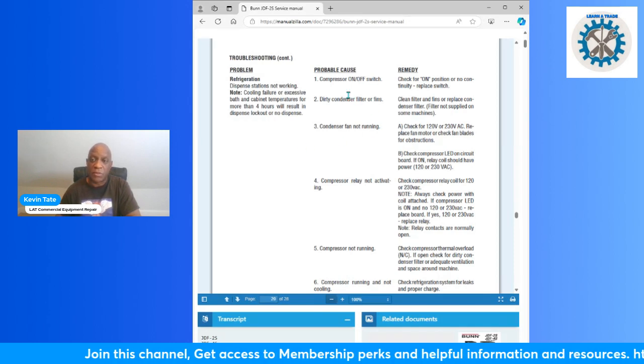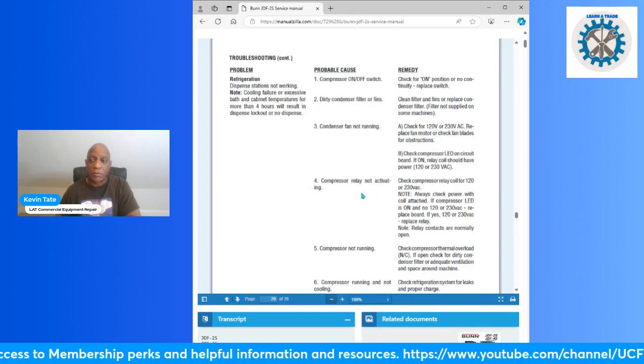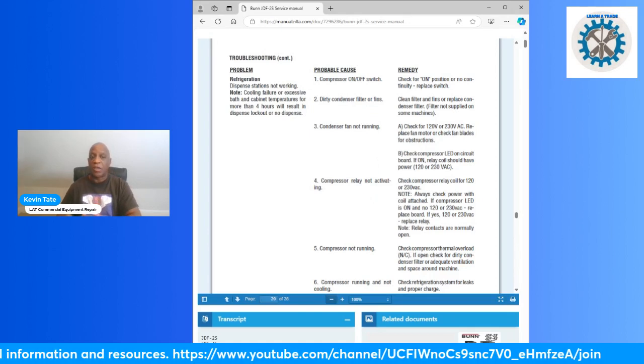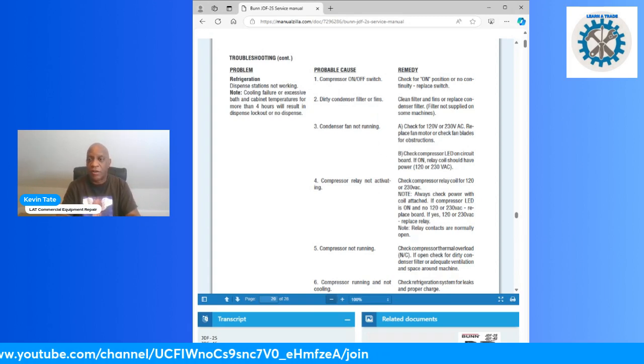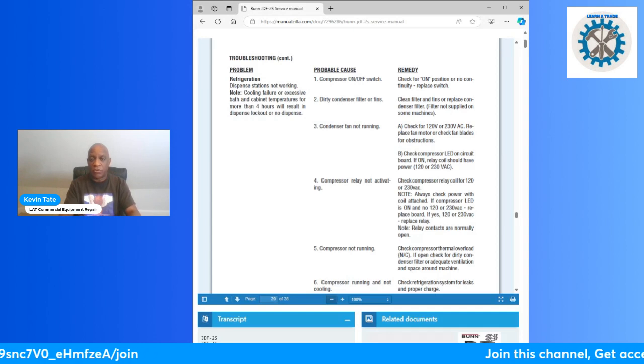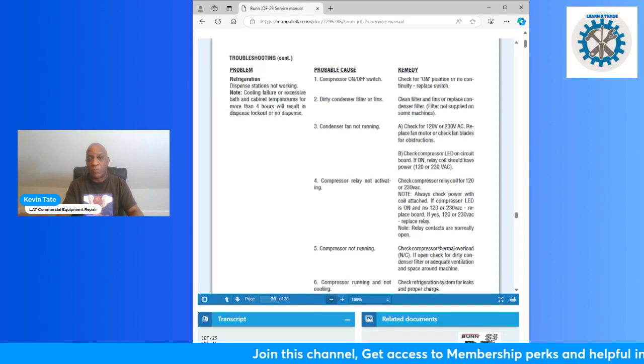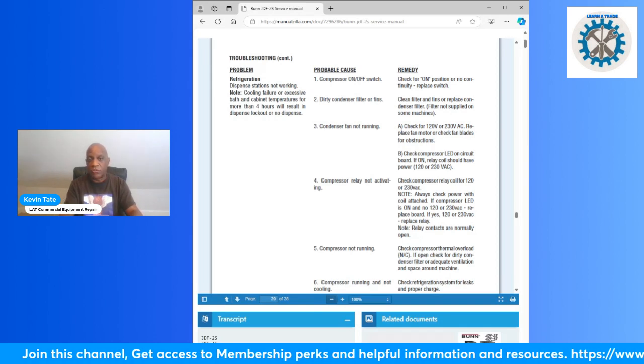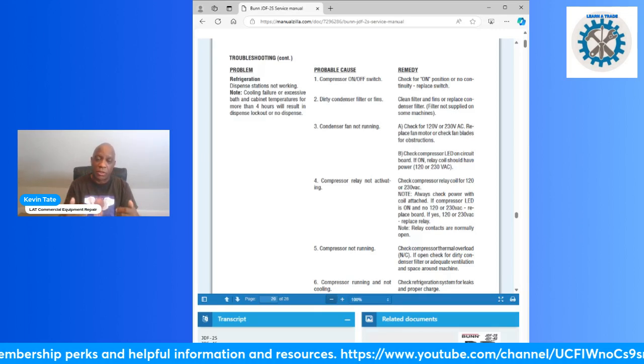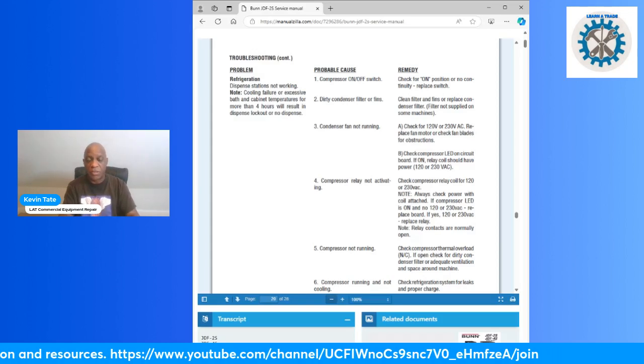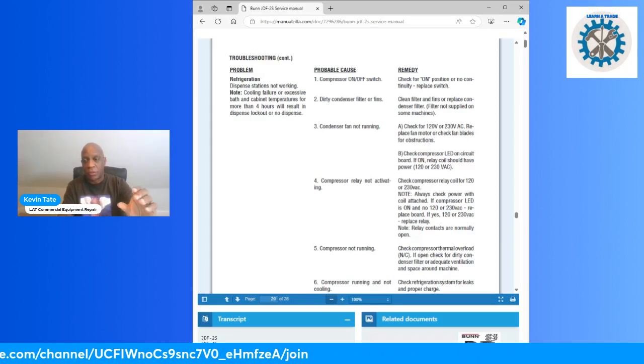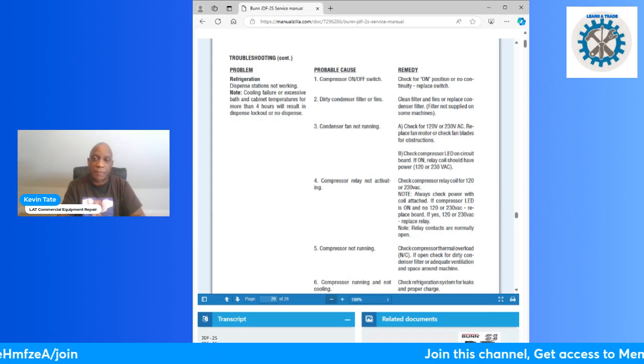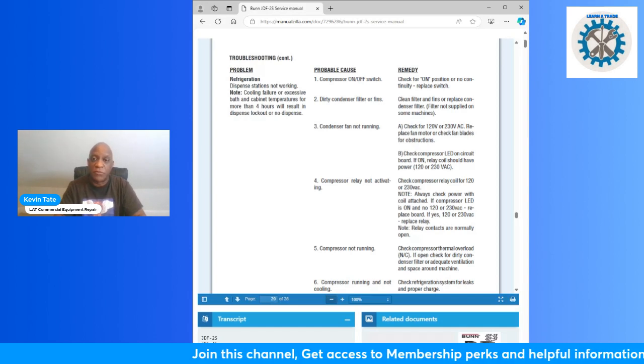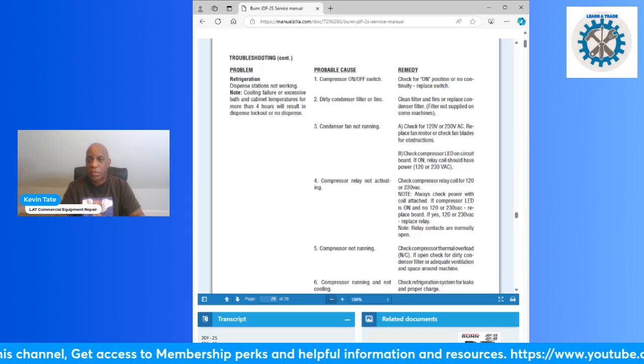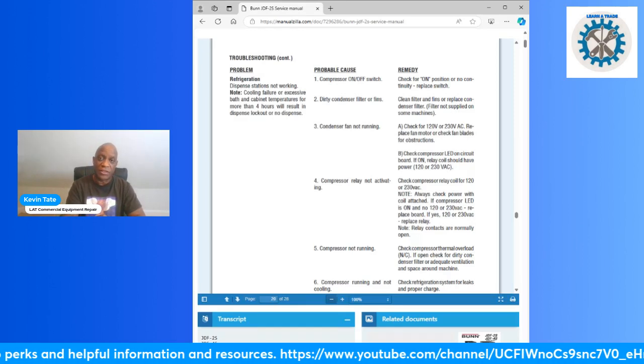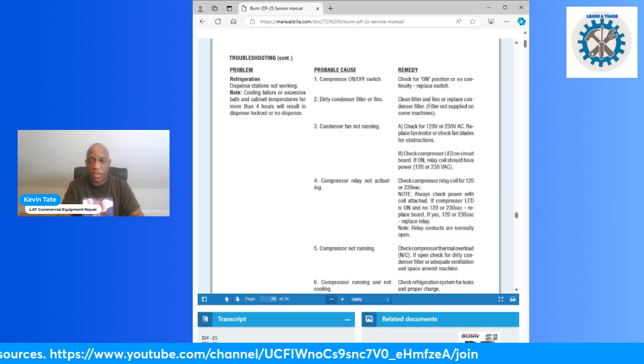Some of the causes could be the compressor on-off switch. You want to check that compressor on-off switch. For those who may not be familiar, that on-off switch is down on the lower section of the JDF2. There's a panel down below held in by two slotted screws. Remove those two screws, pull out the panel, and then you'll be able to see the compressor switch on the top left side of the inside of the lower portion of the machine. You'll be able to see it right there. It's an on-off switch, and some of them have a program switch right underneath that on-off switch for the compressor. So check that out also.